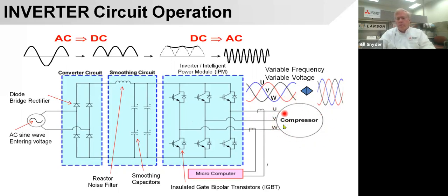So if you had 3 electrical lines going to a compressor, you would typically think that's a 3-phase compressor. And basically it is a three-phase compressor the way it's wired. The signal going to it is, we're varying the voltage now and the sine wave or the frequency. So it's no longer going to be 60 hertz or 60 cycles. It's going to be something other than 60, depending upon how fast we want that compressor to run, and the voltage will vary. When we do that, it doesn't overheat. If you just put a resistor in the line, the windings would overheat and we'd burn up the compressor. When we're chopping the sine wave, we're able to run that compressor really cool, really efficient at a very slow speed or very fast speed.